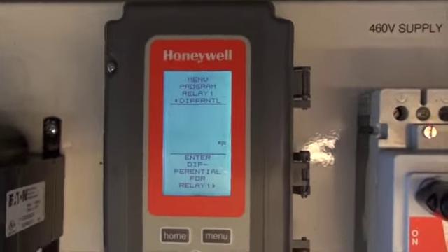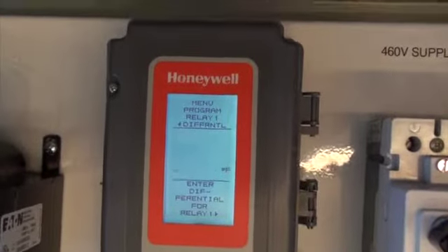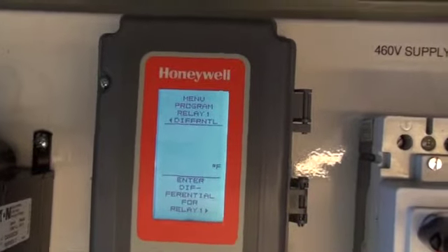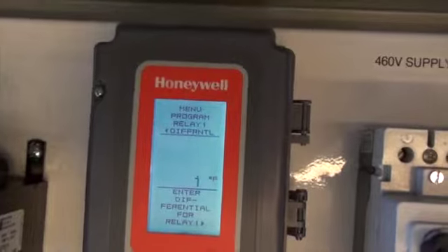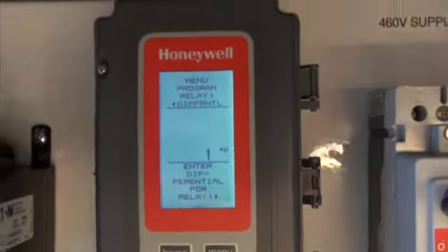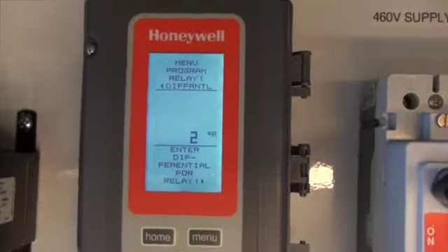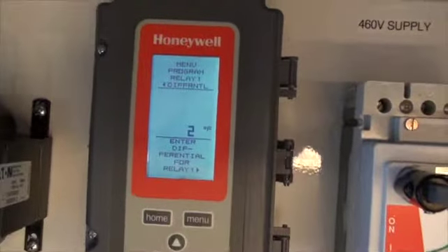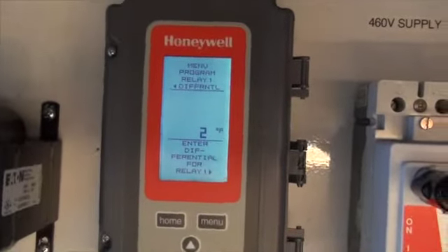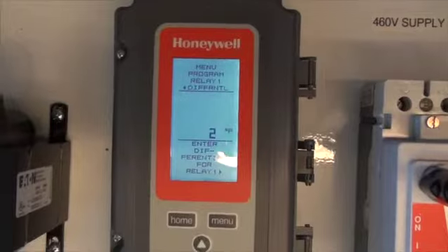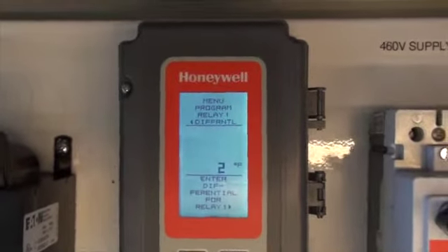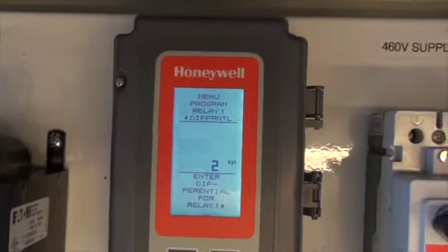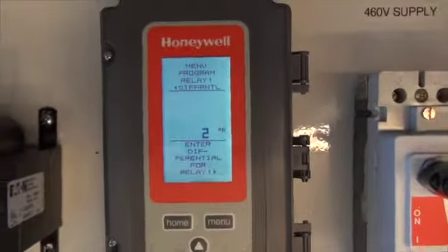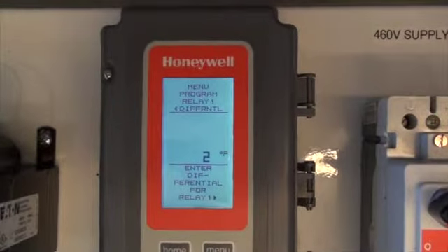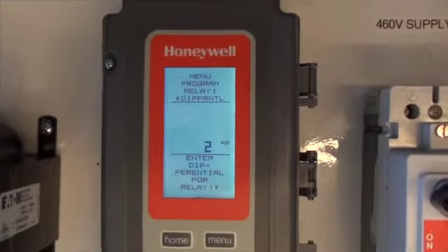In other words, at a 75 degree set point, the spray pump comes on at 75 and will shut off at 74 degrees, which is fine in a spray pump application. You might sometimes want to have that 2 degrees, but I wouldn't go much higher than that because it takes a lot to satisfy. If your set point is 75 and your differential is 5, that means the spray pump's not going to come off till the water temperature is 70 degrees. That's hard to do. So I usually like to set my spray pump at 74, 75 degrees.